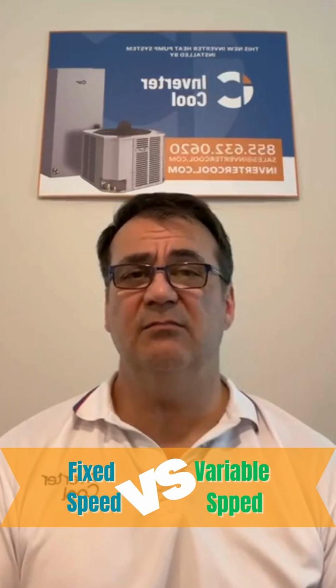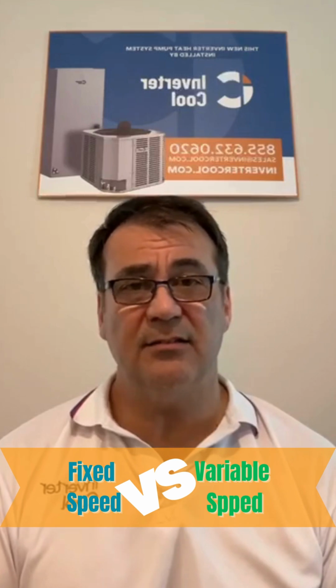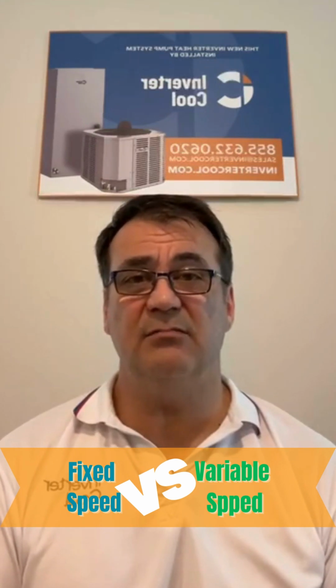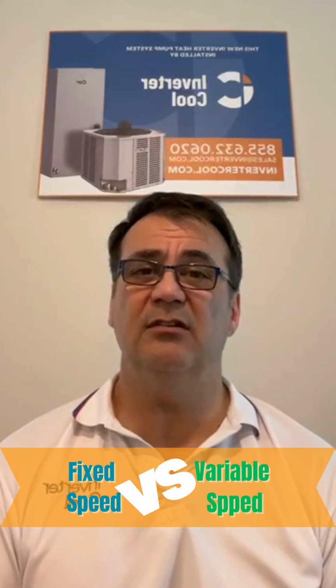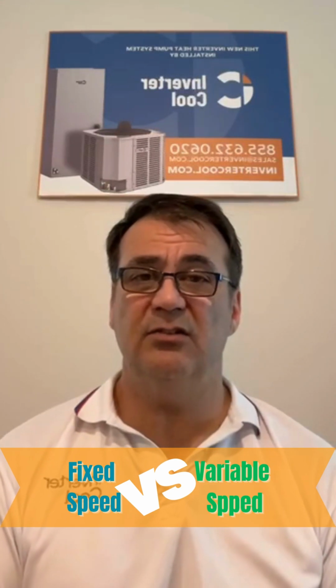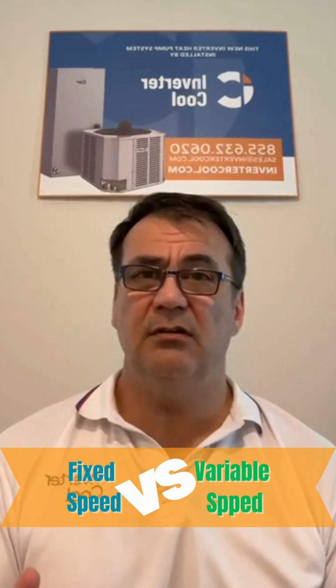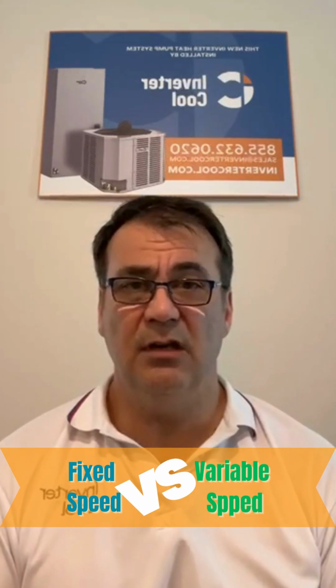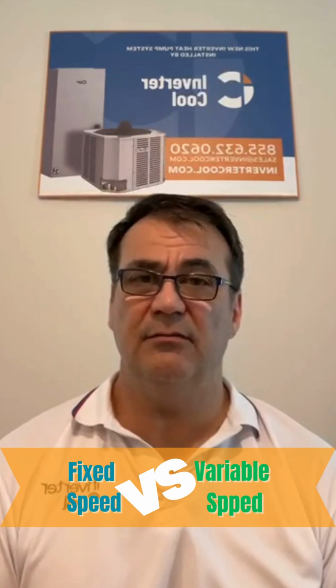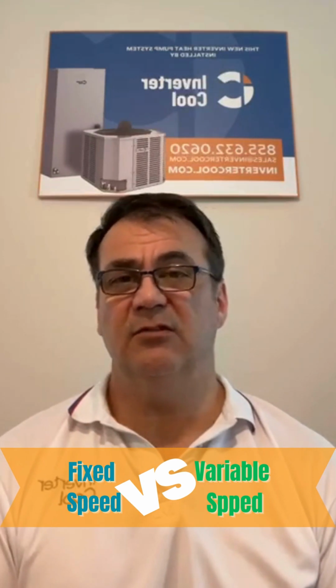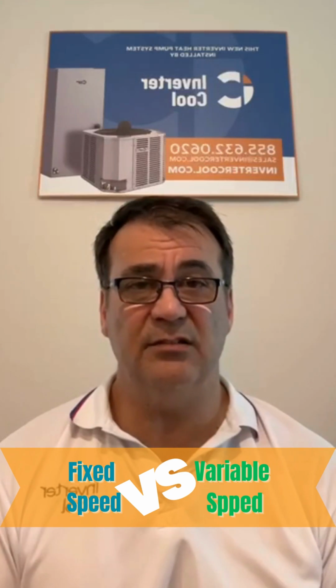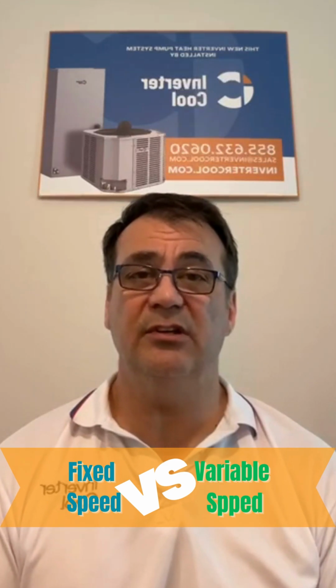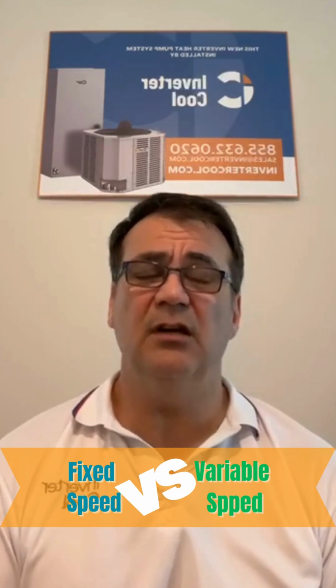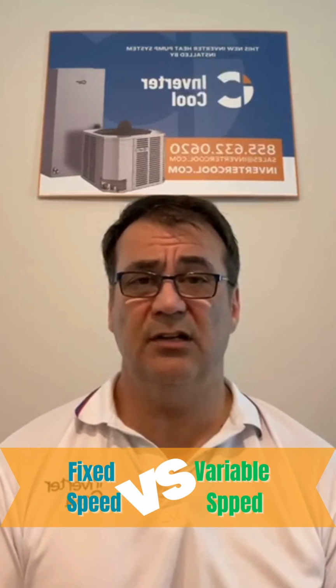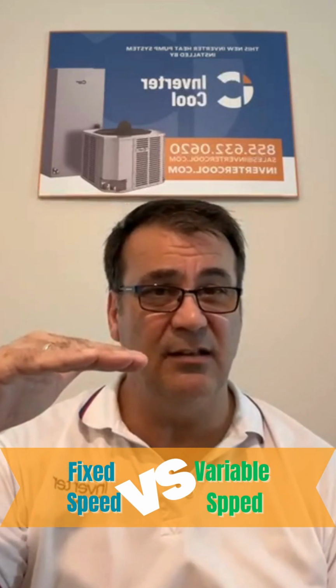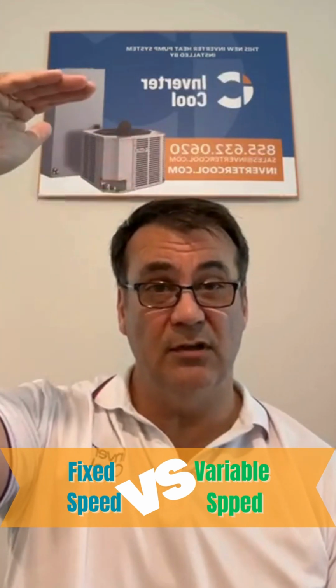An inverter system, when installed properly, can outlast a fixed speed system. And the reason why is because of the varying load conditions. There's no hard startup when the system turns on, and there's no clunk when it shuts off. So this results in a lot less wear on your compressor. It will help lower your energy bills because most of the time an inverter is actually going to run at a partial capacity instead of running full bore.